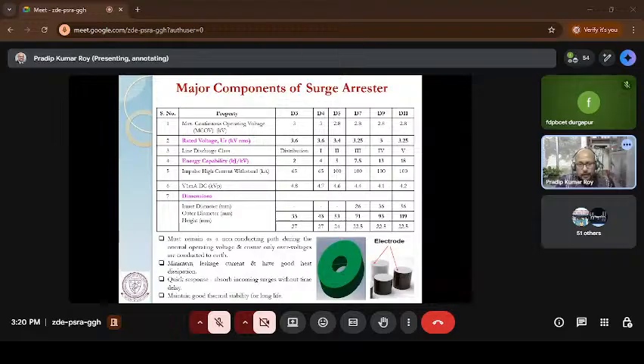Okay, and now these different kinds of blocks have different rated voltages, energy handling capabilities, as well as dimensions. Mostly, D3 is defined with diameter 33, D4 is 43, D5 is 53. So the diameter is different. Now if the diameter is increasing, that means the amount of current passing through the block is high. That's why, as soon as the diameter increases, your energy handling capability also increases. That means the amount of current passing through the block is very high.